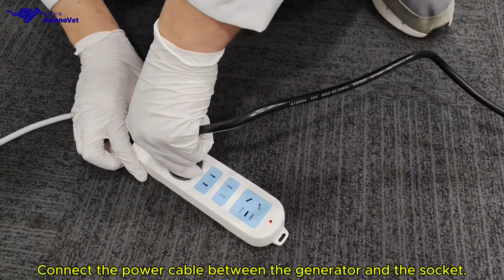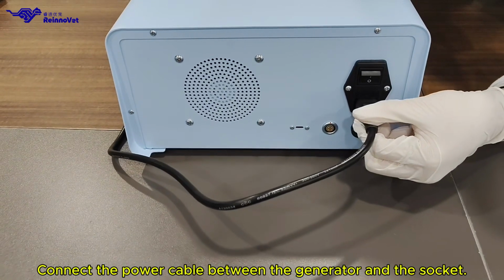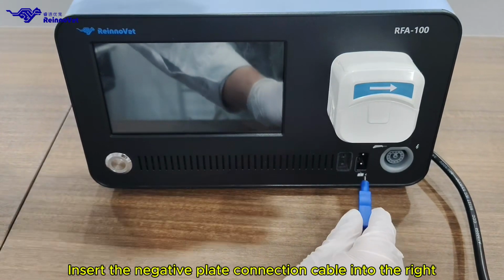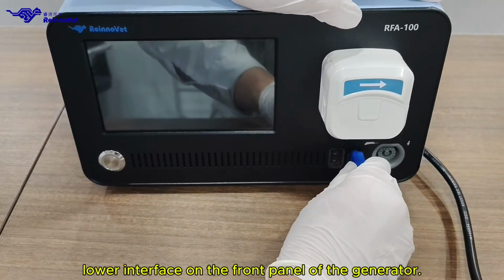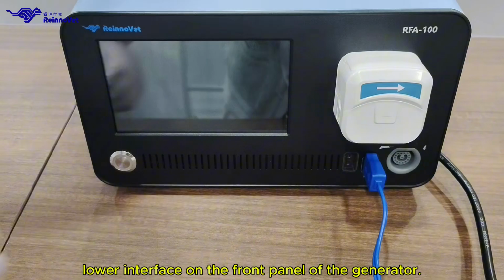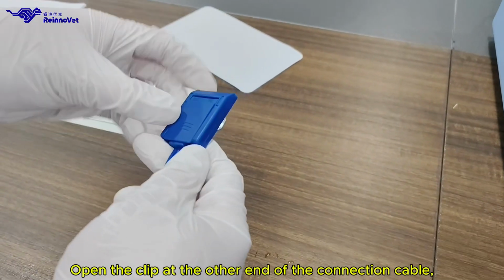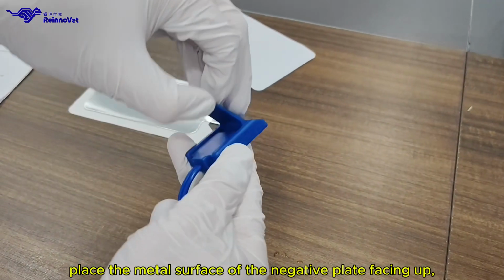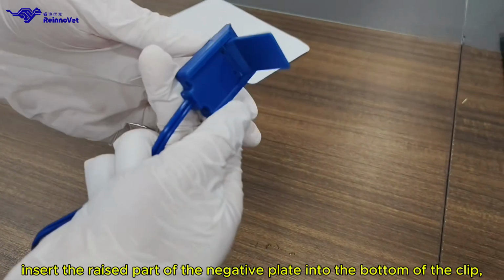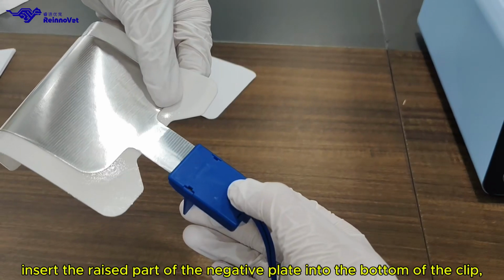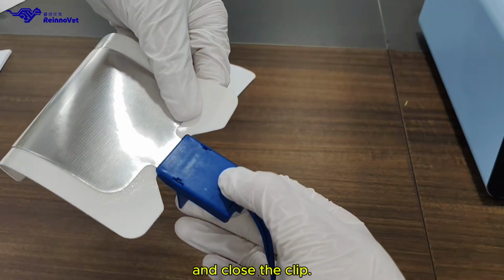Connect the power cable between the generator and the socket. Insert the negative plate connection cable into the right lower interface on the front panel of the generator. Open the clip at the other end of the connection cable. Place the metal surface of the negative plate facing up. Insert the raised part of the negative plate into the bottom of the clip and close the clip.